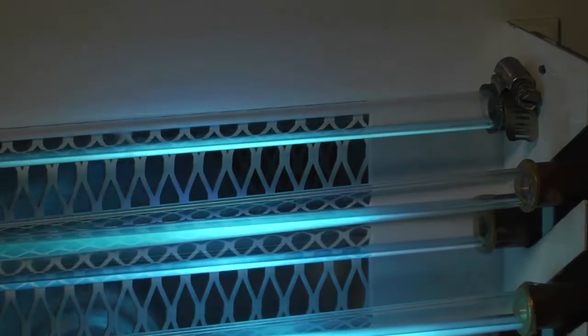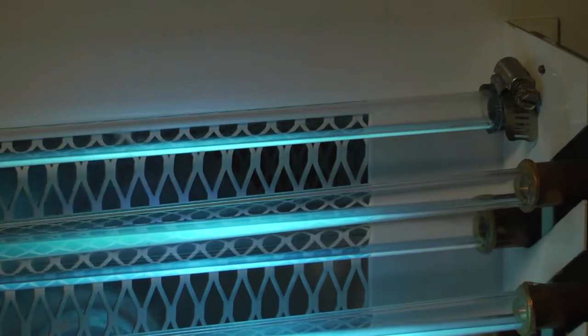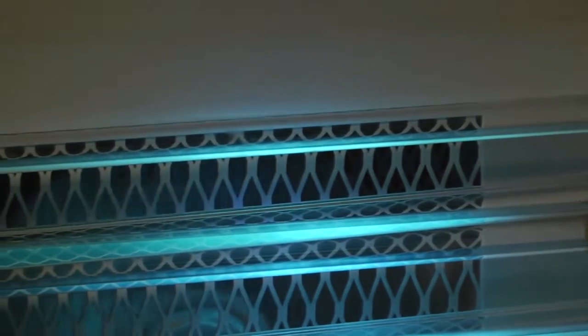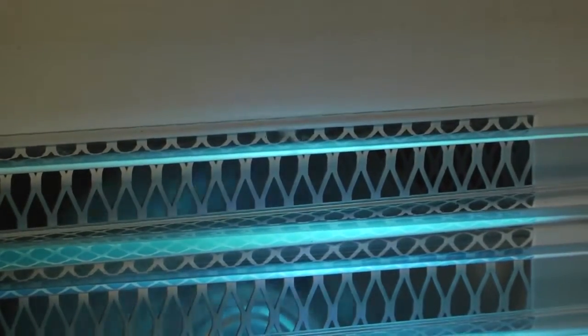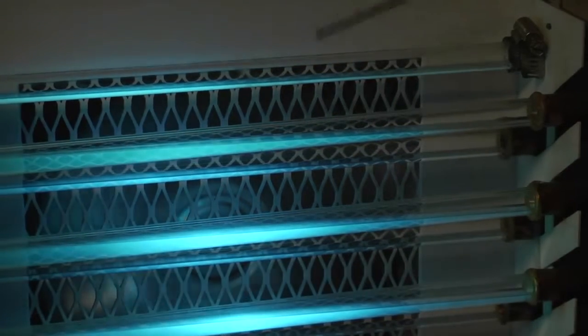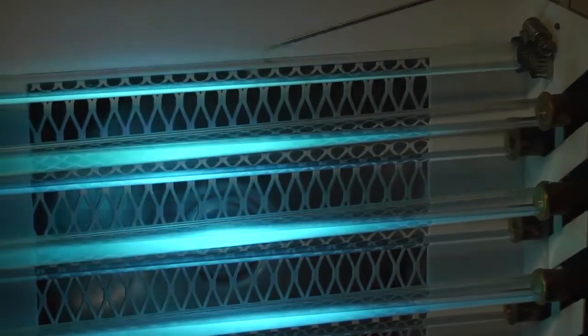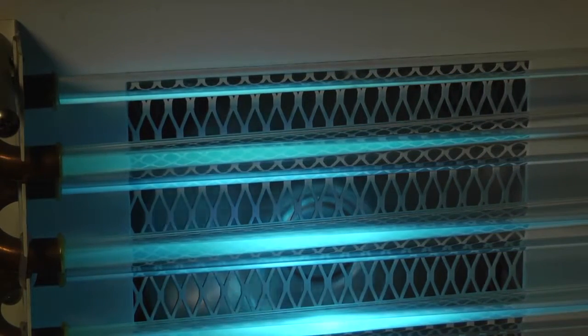It's 100% gas. The first thing the condenser does, now that the compressor has raised the temperature of the refrigerant above the temperature of the room air that's passing over it, is start to throw the heat away from the refrigerant to the air passing over it. And what we can see in this first row is that some refrigerant liquid is starting to form. As that refrigerant liquid is starting to form, we are dropping to the saturation point, doing the first thing that takes place in a condenser coil, the de-superheating of the refrigerant, or bringing it back down to its boiling or condensing point.